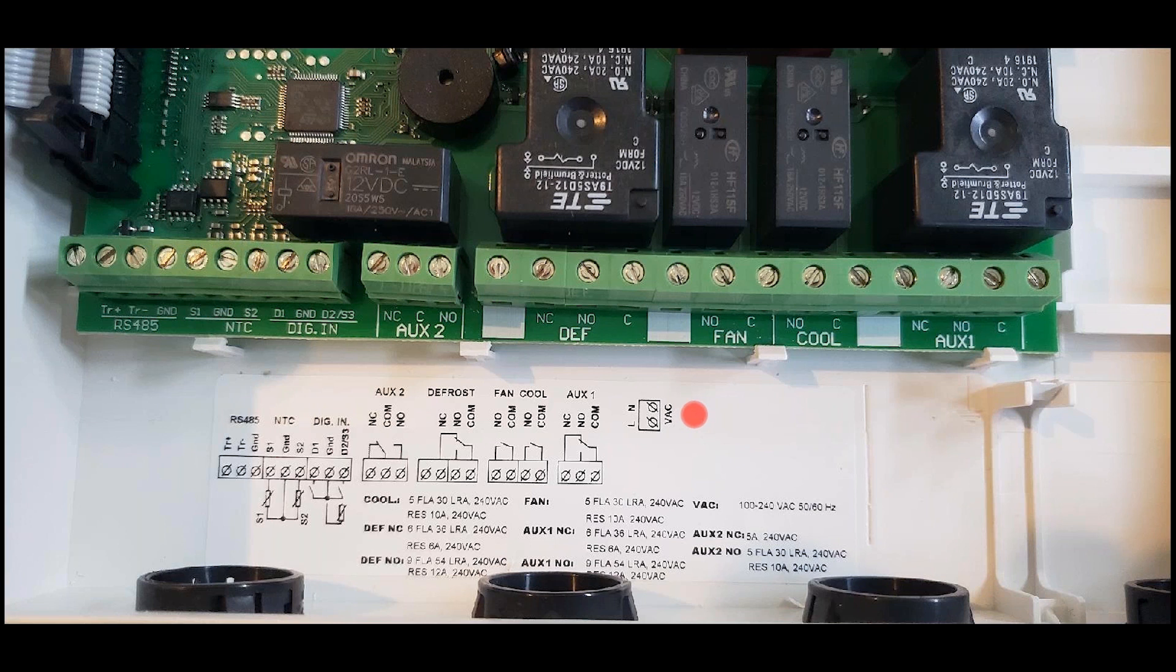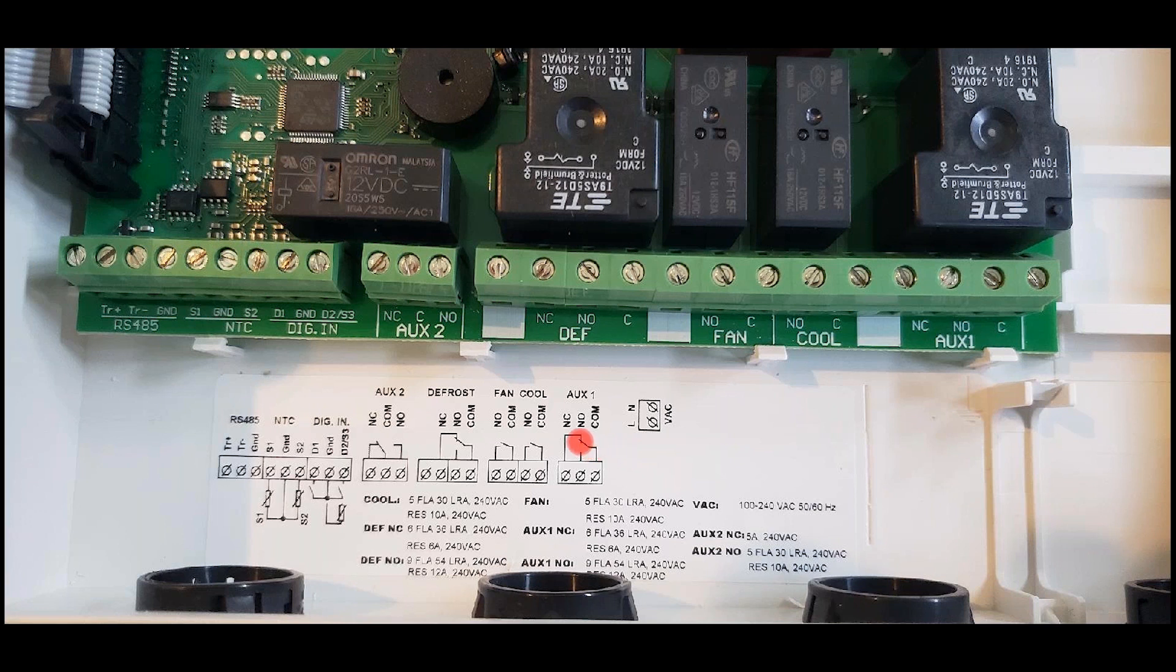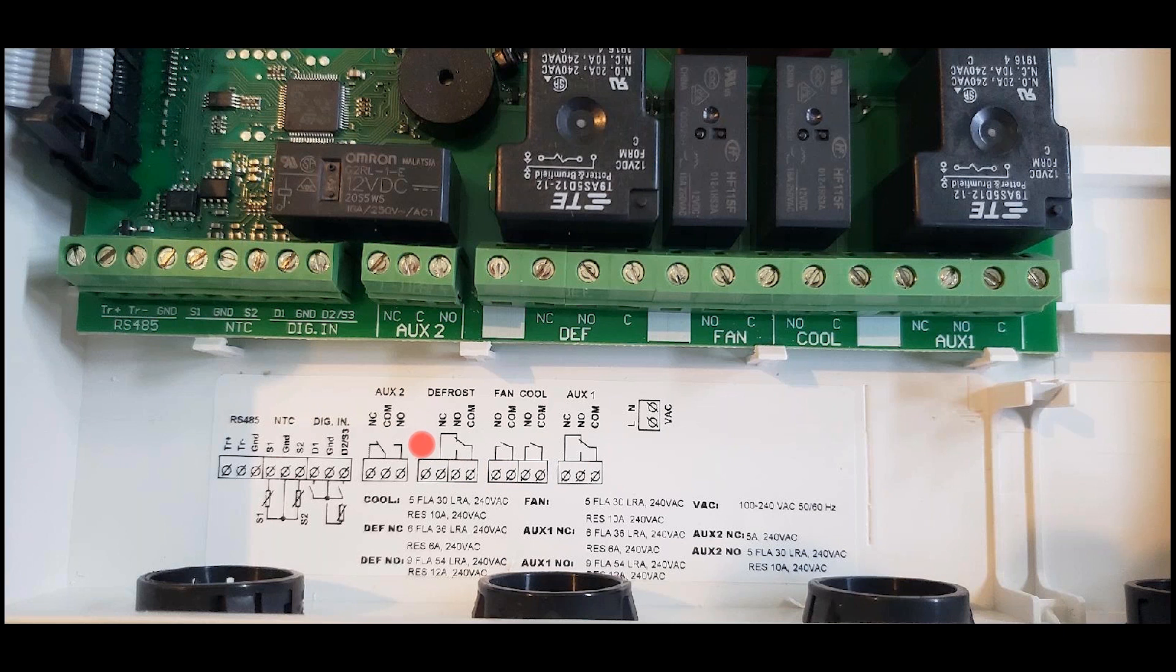To start with, you have your power to the controller, L and N. This powers the controller and only the controller. In other words, we call these dry contacts here. You will need to bring separate power into the common of each of these contacts, and then select which one—normally open or normally closed—that you want to use based on the required function. So each one of these will have their own requirement for power.